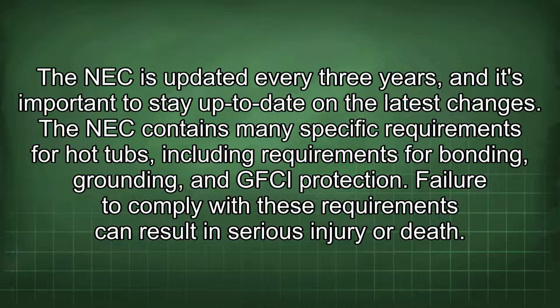The NEC is updated every 3 years, and it's important to stay up to date on the latest changes. The NEC contains many specific requirements for hot tubs, including requirements for bonding, grounding, and GFCI protection. Failure to comply with these requirements can result in serious injury or death.